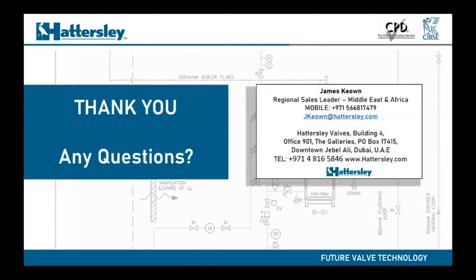The last question is how to calculate valve authority. I think you elaborated on that before, but if you can give a high-level brief on that. No problems. Basically, it would be the differential pressure across your 2-port control valve divided by your differential pressure across your circuit. Now, for a DPCV, that includes all the pipe work from your impulse tube connection through your index to your coil, through all your valves and back to the DPCV. And therefore, with the examples that you saw in that presentation, the smaller the groupings, the better the valve authority.